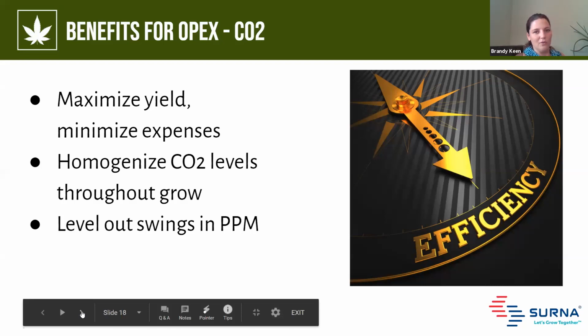Automating the delivery of CO2 to your room makes sure it stays between 1200 and 1500 parts per million, or 800 and 1200 parts per million, or whatever that range is — making sure it doesn't get too high, doesn't get too low, and making sure you have the appropriate alarms, which your fire department's going to require anyway.